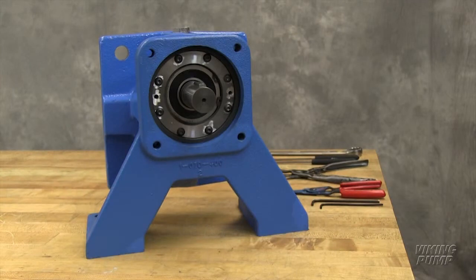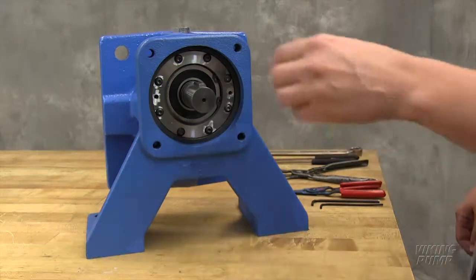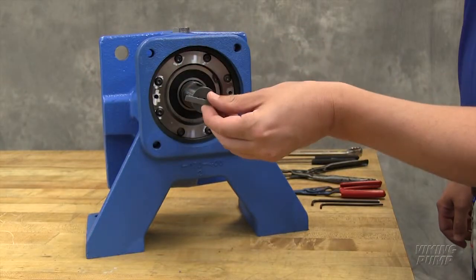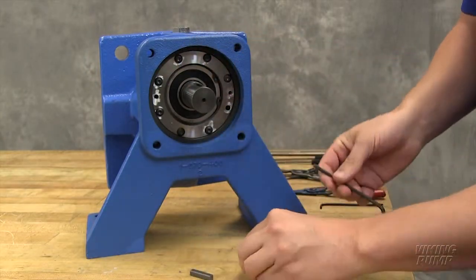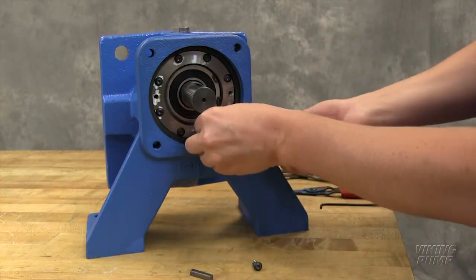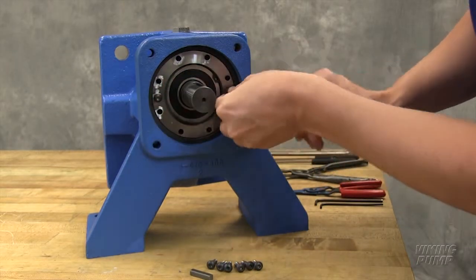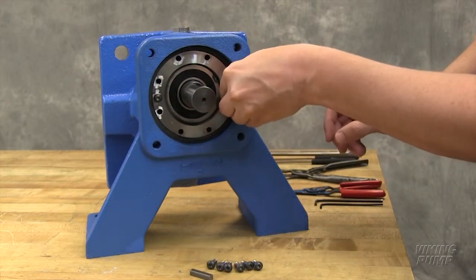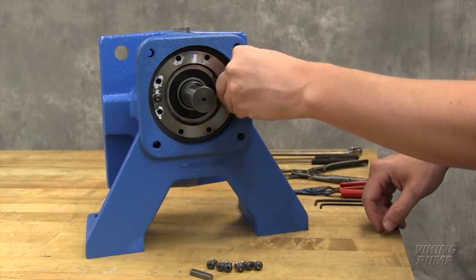Vent all the pressure inside the pump prior to removal of the seal. Keep the pump and work area as clean as possible. Drain the pump of any residual liquid. Turning the shaft will help expel any liquid trapped in the gear teeth. Remove the pump drive coupling and drive key. Loosen and remove the seal holder cap screws. Use 2 of these cap screws as jacking screws to remove the seal holder slowly from the pump bracket.